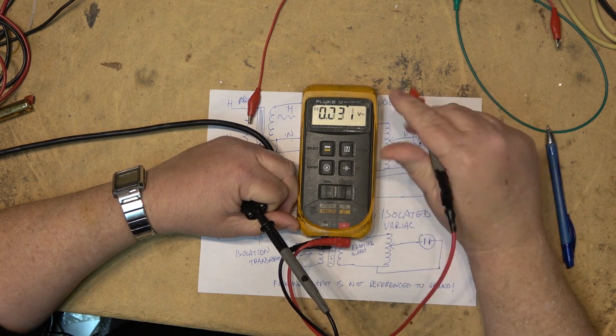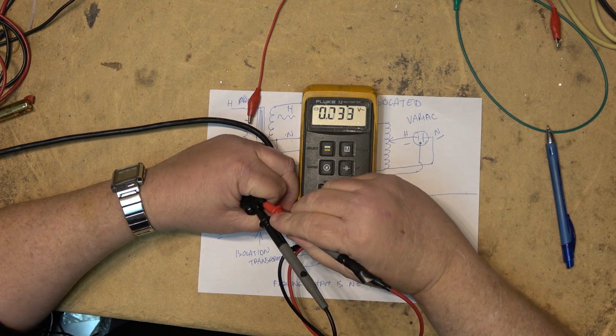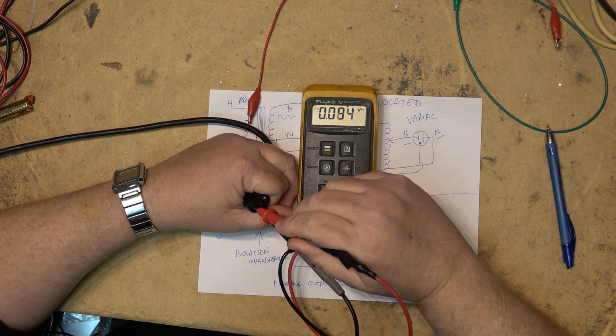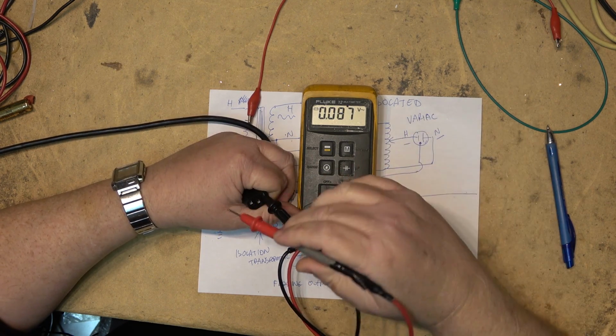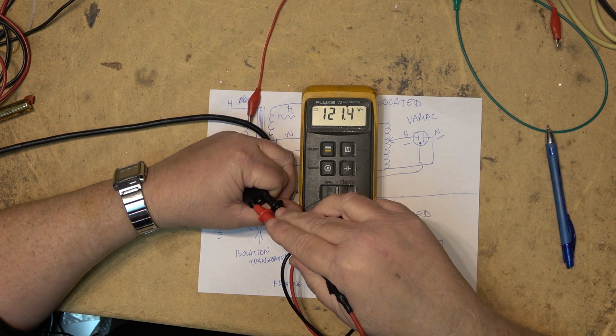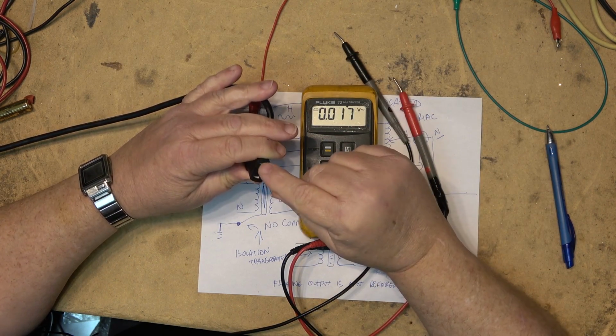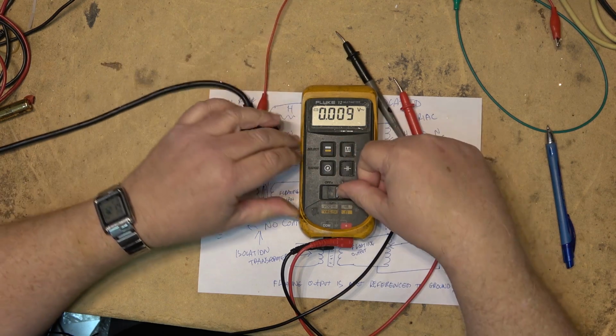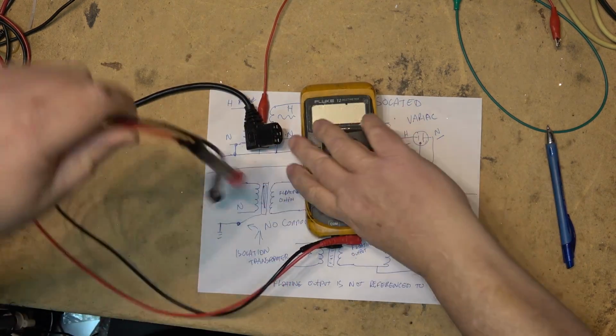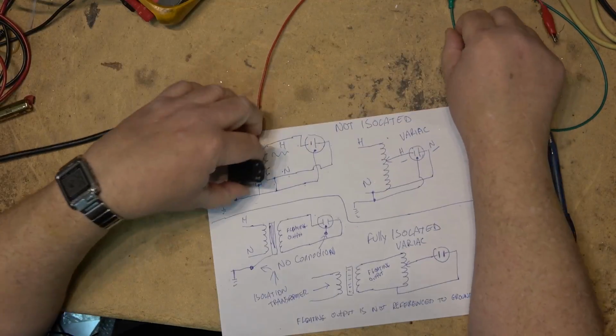It's not much. It was like 0.2 volts. And of course, on the other side, there's 121. If I go between neutral and hot, 121. Anyway, what I'm getting at is the ground and neutral are tied together. It's just that this meter is a little too sensitive. It detects that 0.2 volts and says, I'm not measuring it.